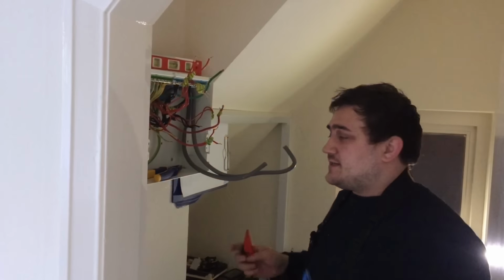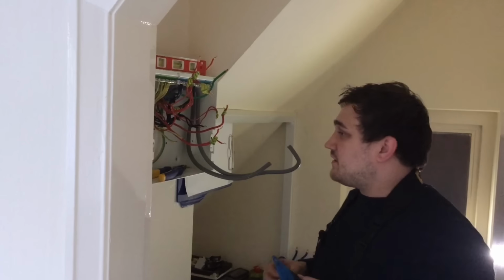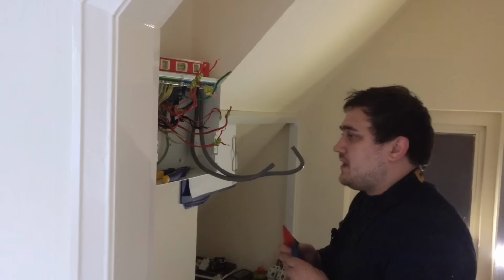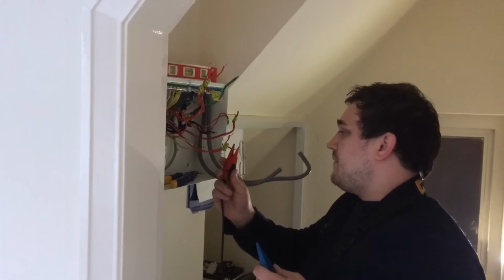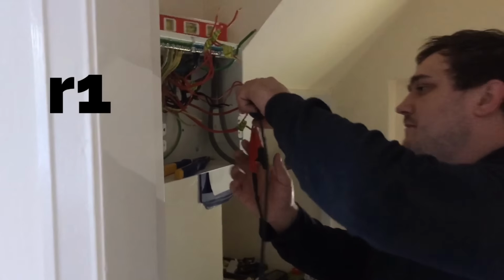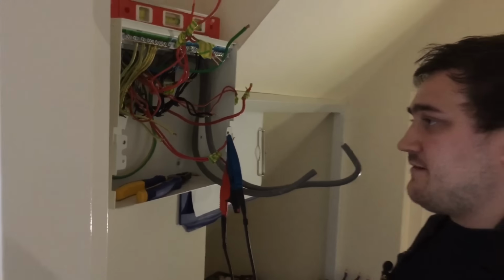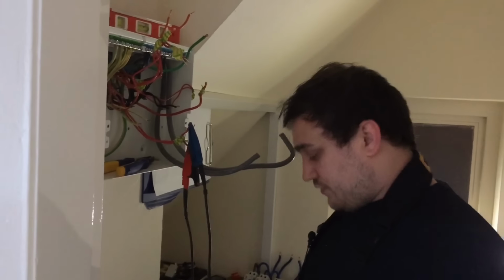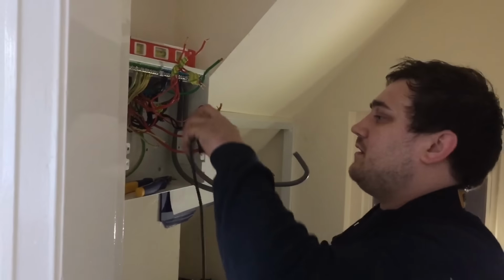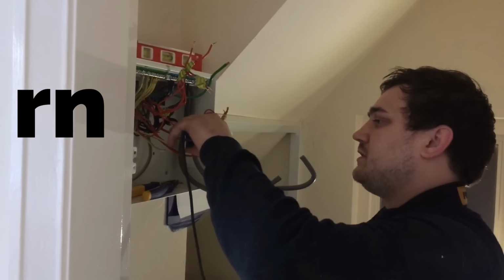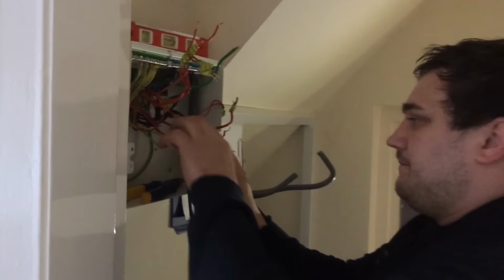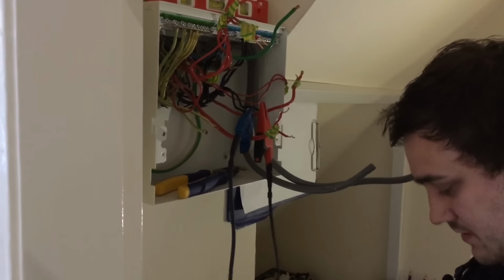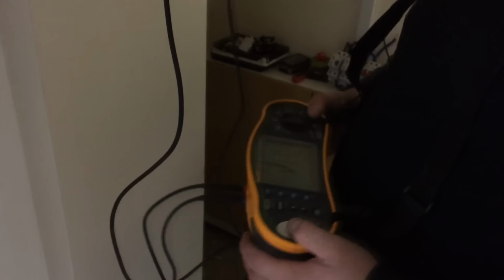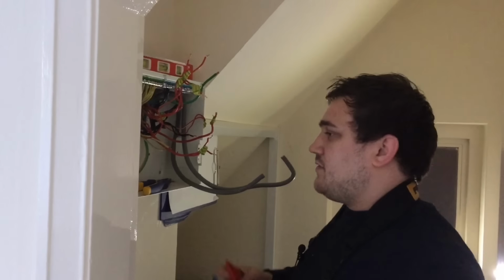Now moved on to the second dead test, which is the continuity of the ring final circuit protective conductor. First of all, I'm going to probe onto the end of my line conductors and prove continuity. This is proving that there's a continuous ring around the circuit. Get a reading of 0.15. Now I'm going to probe onto my neutral conductor. Again, 0.15, which is what we would expect, as there's the same length of cable.